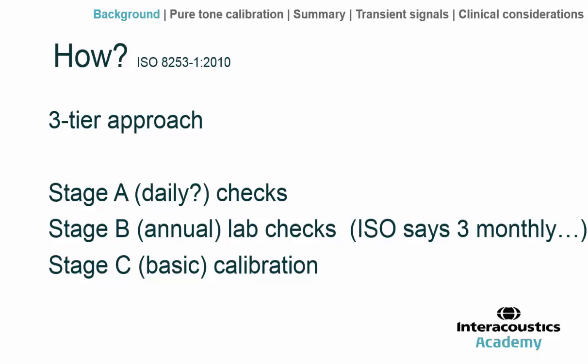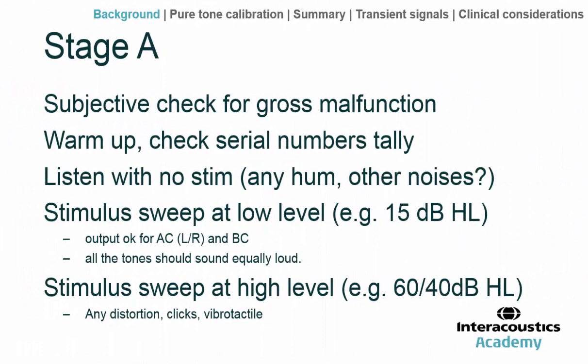Stage B checks might, on a pragmatic level, be performed annually, although international standards suggest three-monthly. Stage C is a very basic series of checks, getting down to the fundamentals of the instrument's workings, performed only once or a handful of times in the whole lifetime of the instrument. Stage A might involve a subjective visual inspection for any gross malfunction — any leads that have been disconnected or fraying.